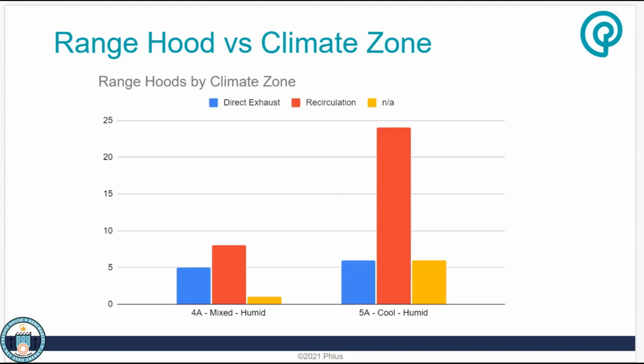It's pretty interesting to see that a lot more projects in 5A were using recirc than direct exhaust, with a more even split in 4A. That makes sense, because introducing direct exhaust increases the losses through the ventilation system. In a colder climate like 5A, direct exhaust is a bigger penalty on heating losses than it would be in 4A.